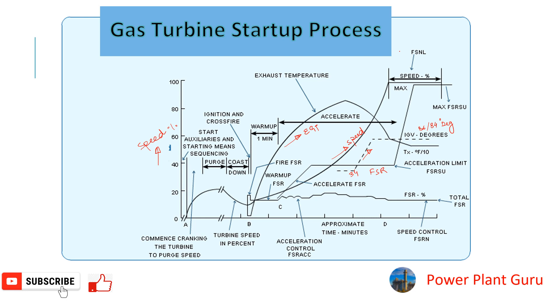Before the turbine breaks from standstill speed there is a sequence related to auxiliary equipment, which we will cover in a different video. You can see the speed increasing a little — the machine is on cranking, which some people call barring and some call ratcheting. For smaller machines like the 6B it is ratcheting, and for larger machines it is barring at around 115 to 120 RPM. The machine is kept under barring until you give the auto start command.